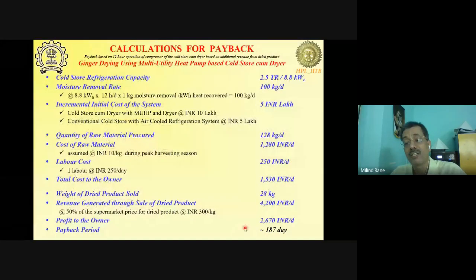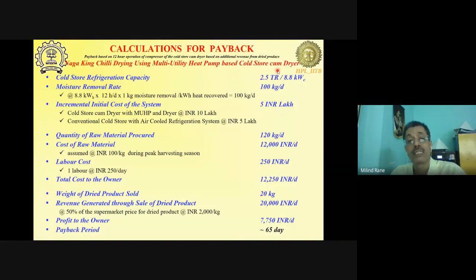And just to come to the economics of this, you can see that the payback here was around 187 days for ginger drying using the heat pump operated to concurrently give cold store and drying utility. Okay. Then for Naga chilies, which are a very high value product, the payback went down to just 65 days, for the cost of the heat pump and the cost of the dryer and other things.